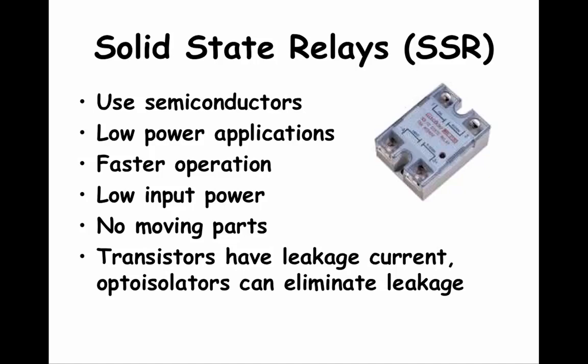One disadvantage of solid-state relays is that some may have what is called a leakage current — the current flow that continues to pass through on the load side of the circuit even though the control side says to open the circuit. Leakage current is inherent in semiconductors. It may not be a problem with some loads, but if it is a problem, it can be managed with opto-isolators.